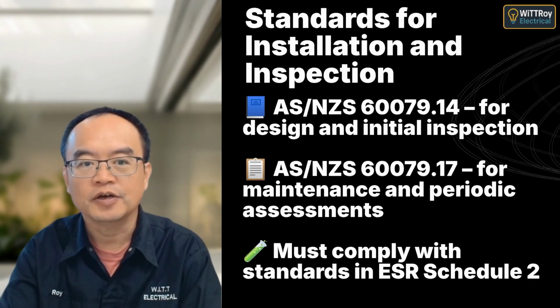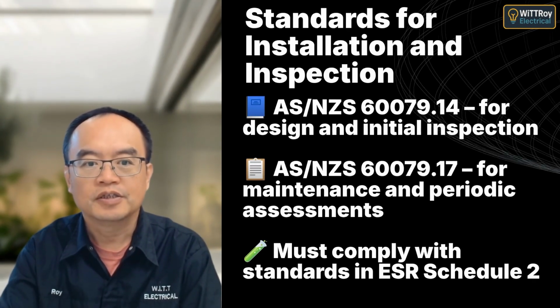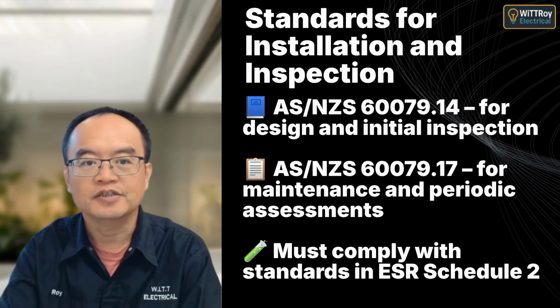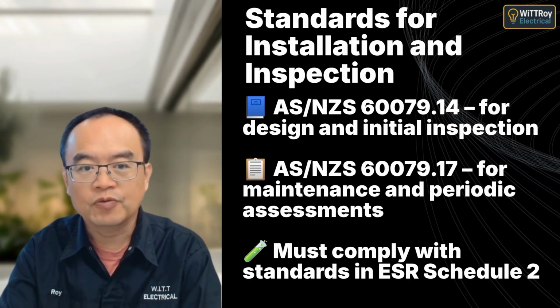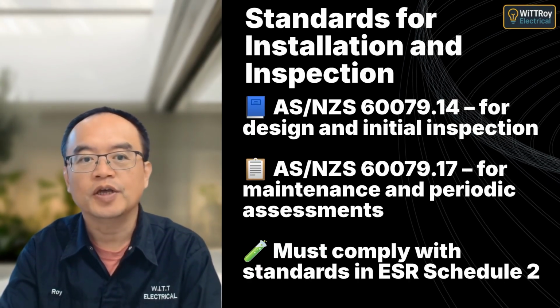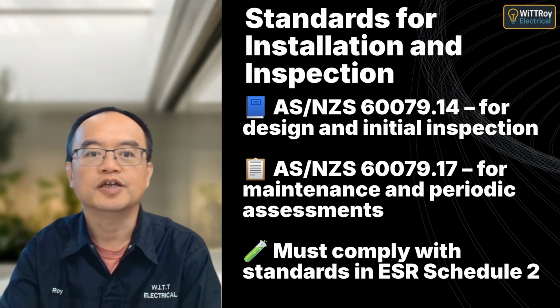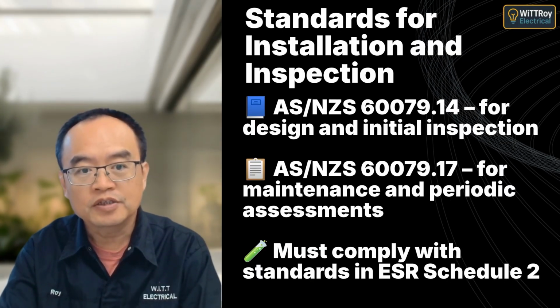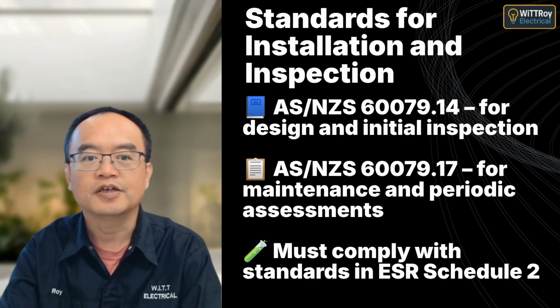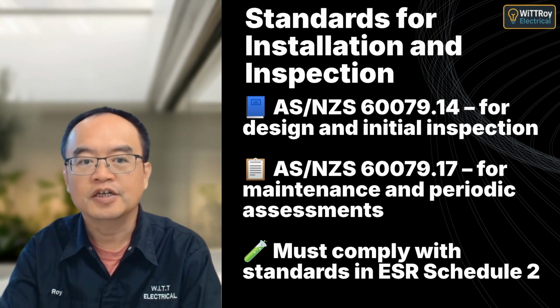Installations in hazardous areas must be designed and initially inspected according to AS/NZS 60079.14, which includes selecting and erecting equipment based on gas classification and zone. For ongoing maintenance and testing, AS/NZS 60079.17 applies. These standards are referenced in ESR Schedule 2, making compliance mandatory.